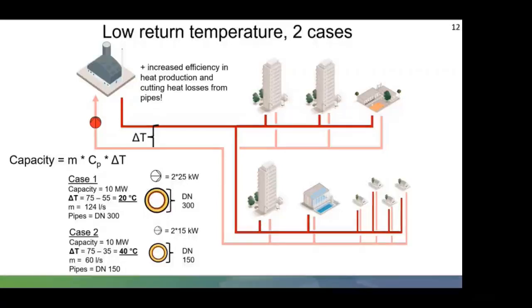So case two. Case two has the same primary flow of 75 degrees, but the return has been reduced to 35 degrees. Now you've got a delta T of 40 degrees, dropping the mass flow to 60 litres a second. By lowering the return temperature and using more of the heat in the flow, we can reduce the pipe size to DN 150 and reduce the size of the pumps required to 2 times 15 kilowatts.